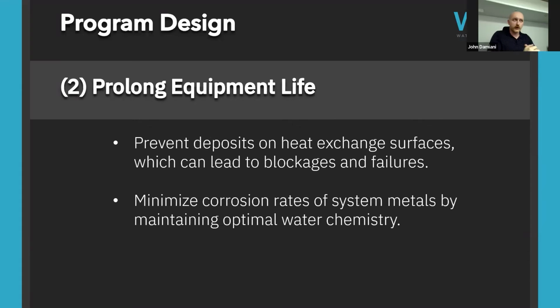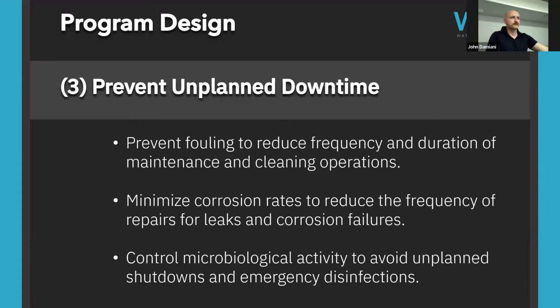The second one, prolonging equipment life. So how do we do that? Well, number 1, if we prevent deposits on the heat exchange surfaces, that can lead to blockages and failures, which would lead to premature failure. So if we can prevent that, we're helping prolong equipment life. Same with corrosion. So if we minimize the corrosion rates of all the metals in the system by maintaining the best water chemistry, that will extend the life of the equipment as well, and the piping.